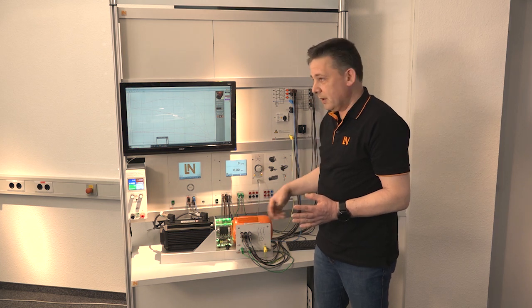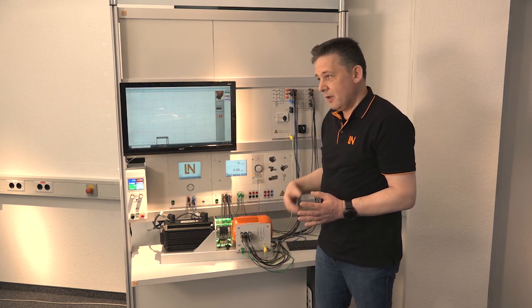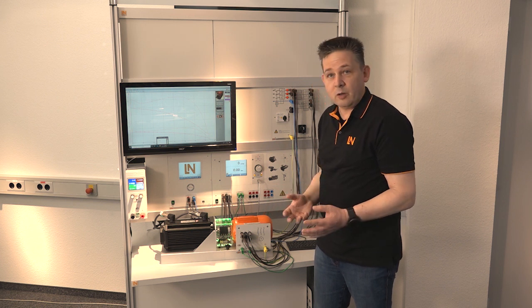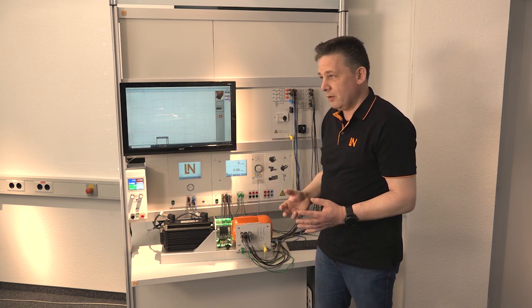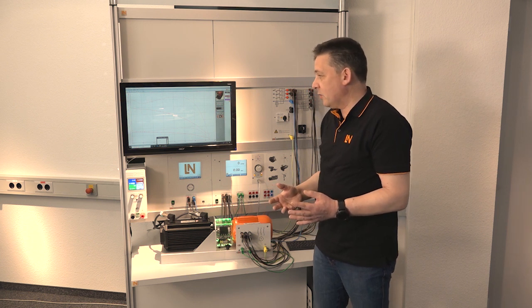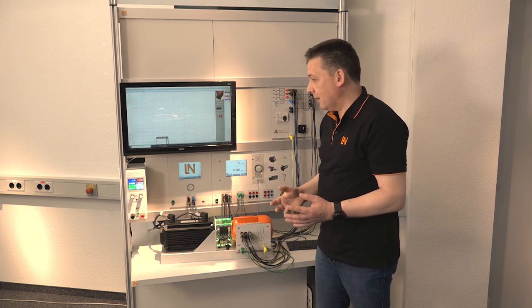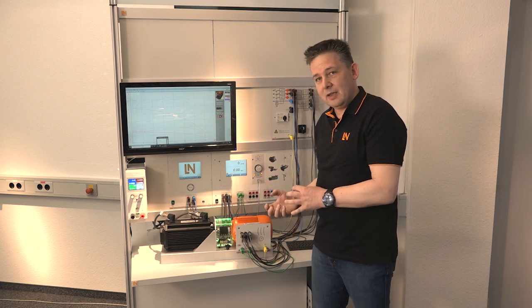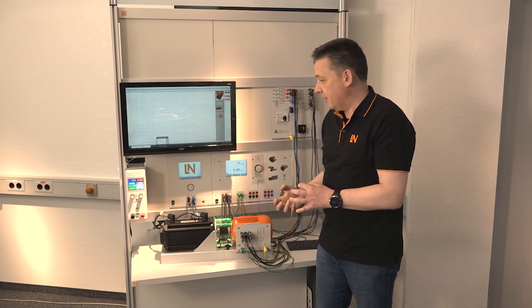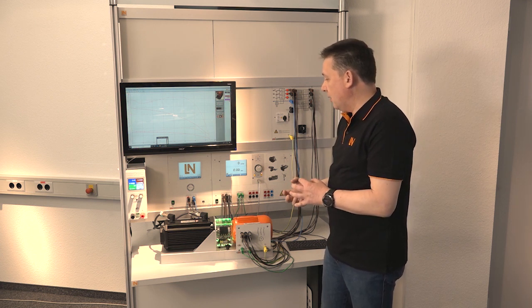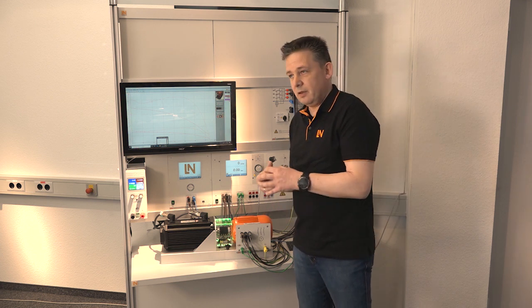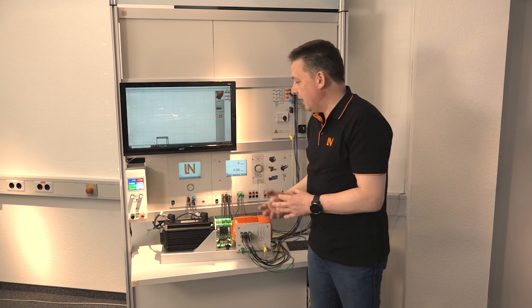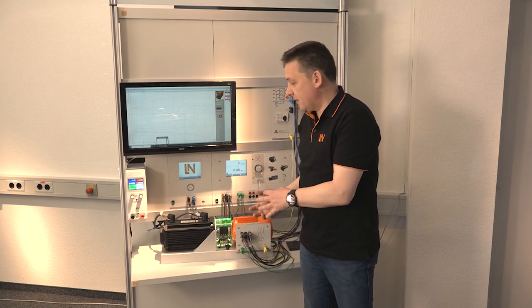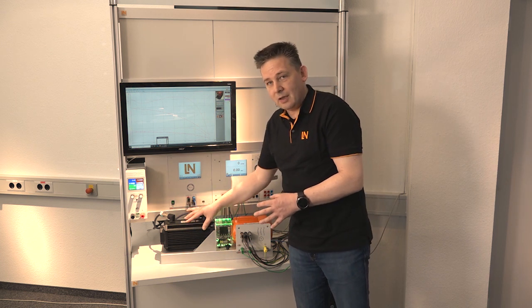Now we have seen one side of the medal. We have looked at the motor side, but motors in the industry are not only motors, they are applied to drive a working machine. And now we come to the working machine. For example, we have in the industry a big ventilator, and the idea is now to bring this ventilator into the laboratory. So what we did in the software or in the system, we implement the characteristic of the ventilator in our servo machine test system. So the black unit behaves now like this ventilator.